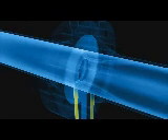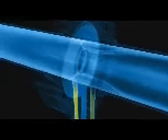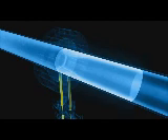As soon as the fluid starts to flow, its velocity around the orifice plate increases significantly because of the restriction in the cross-section. At the same time, due to the laws of fluid mechanics, the static pressure at this point decreases. Consequently, different values are detected in the pressure chambers of the sensor, a higher pressure before and a lower pressure after the orifice plate. This pressure difference is a direct measure for the flow velocity, and thus the mass and volume flow in the pipe.